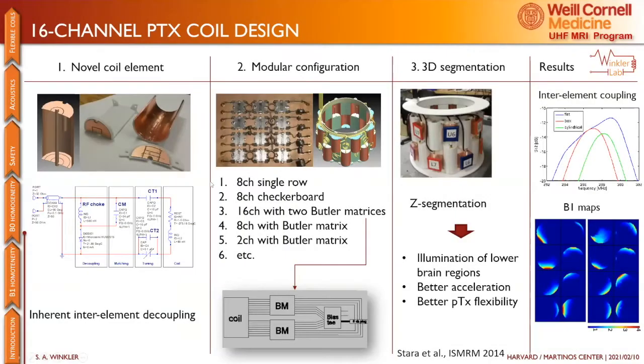So the next one is a fairly old design. I just wanted to bring it up because it's interesting what kinds of coils you can think of at 7T. Here we, with Ricardo Starra, a few years ago, made a 2-row head coil, 16 channels. It can either be driven using a single row or a checkerboard, or you can drive all 16 with Butler matrices. So that was really cool. And in order to avoid inter-element coupling, he came up with this shield around each element. So that helped a lot too. Yeah, and the Z segmentation with the rows helps you to get a little bit of control in the SI direction as well. So that's a little bit similar to our body coil design, but not really.